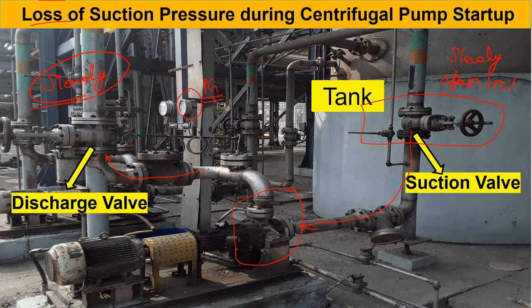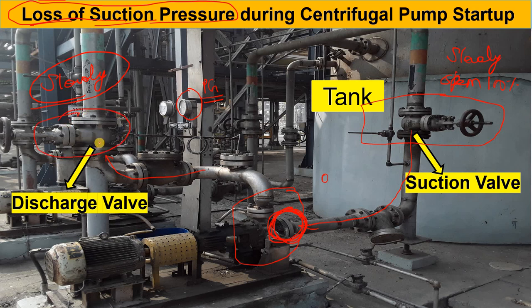Now, when does this problem occur — the loss of suction pressure? At the suction side, inside the centrifugal pump there is the impeller and there is the eye of the impeller, where the pressure is minimum. If the pressure is minimum, the velocity is maximum. So as you open the pump discharge valve, velocity in the suction line increases, and because of that the pressure at the eye of the impeller — the suction side — decreases.